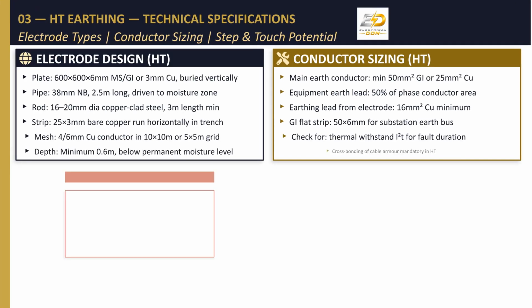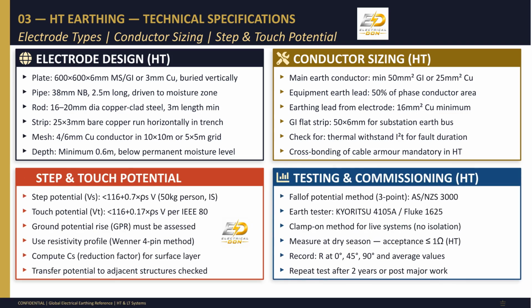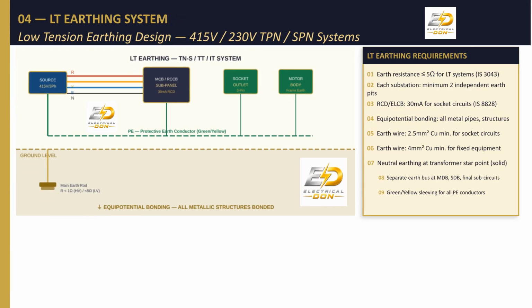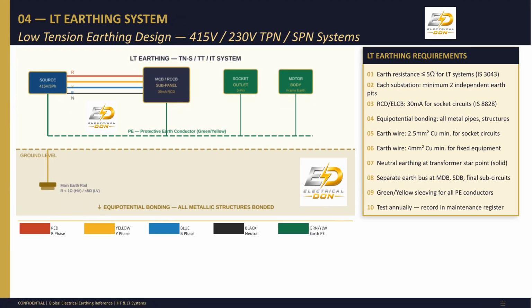HT electrode specifications detail acceptable materials and sizes for plates, pipes, rods, and strips, typically buried at least 0.6 meters deep. Conductor sizing must withstand fault current. Step and touch potential limits are calculated per IS 3043 and IEEE 80. Testing requires a fall of potential test, aiming for below 1 ohm, and repeating tests every 2 years or after major work. LT earthing designs target a maximum resistance of 5 ohms.